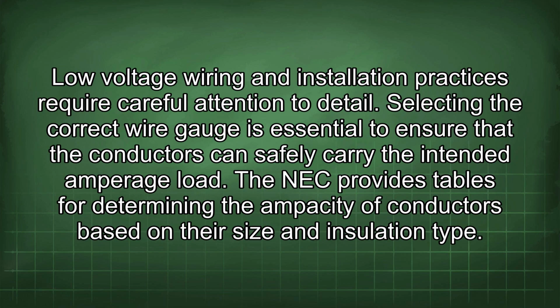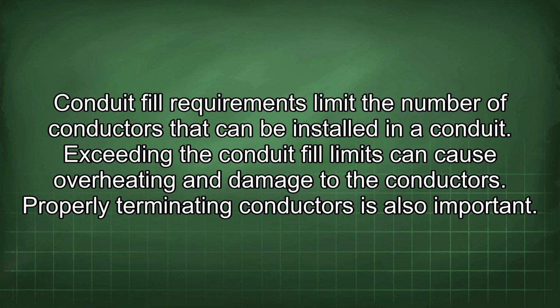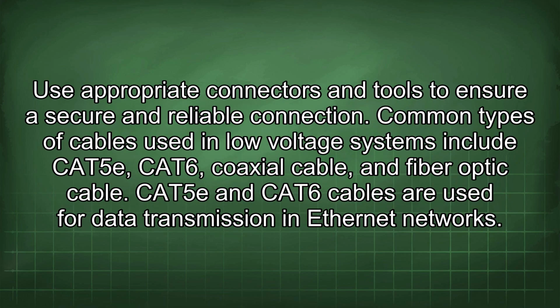Low voltage wiring and installation practices require careful attention to detail. Selecting the correct wire gauge is essential to ensure that the conductors can safely carry the intended amperage load. The NEC provides tables for determining the ampacity of conductors based on their size and insulation type. Conduit fill requirements limit the number of conductors that can be installed in a conduit. Exceeding the conduit fill limits can cause overheating and damage to the conductors. Properly terminating conductors is also important. Use appropriate connectors and tools to ensure a secure and reliable connection.